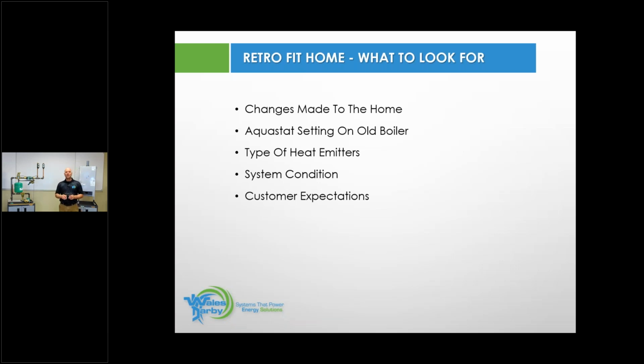So important to know that. The type of heat emitters, that's important because that plays right into system conditions. So if I have an old cast iron system with big 2-inch diameter pipe and I'm going to put a condensing boiler in there, that's a good marriage. Large volume in the system, low volume in the boiler, that's a good marriage. But how do I treat that? How do I treat the water? How do I treat those pipes? How do I get all the dirt and debris out?